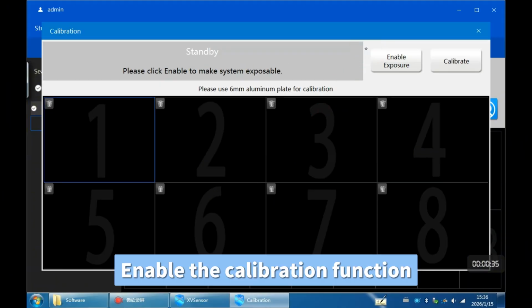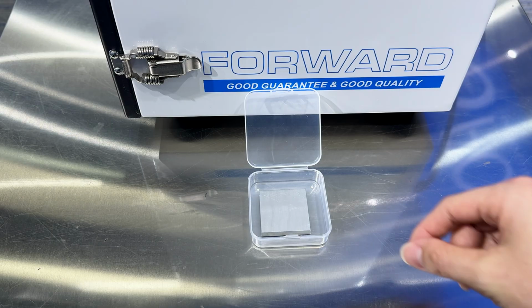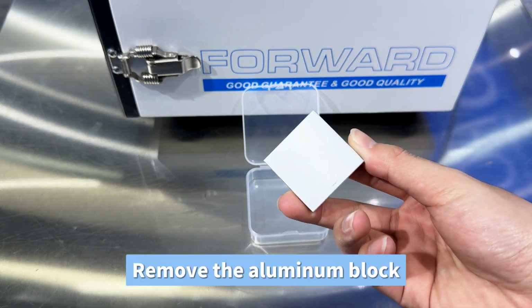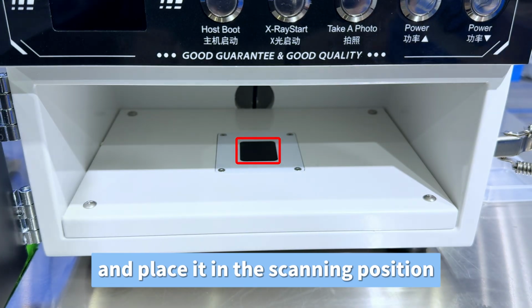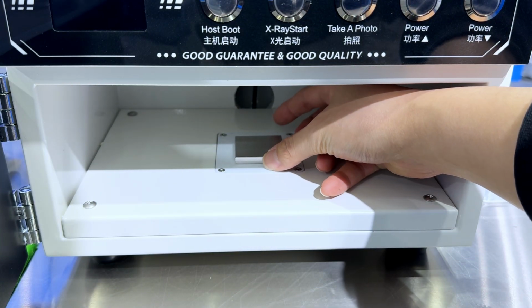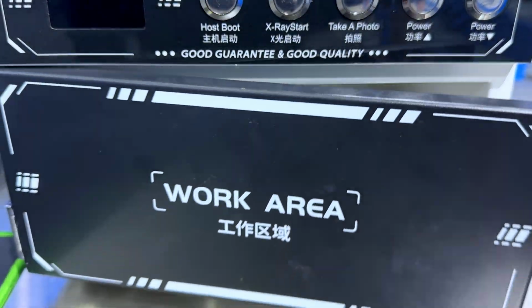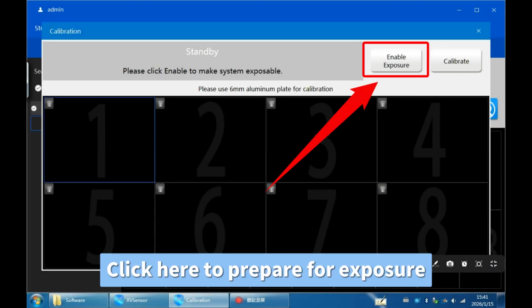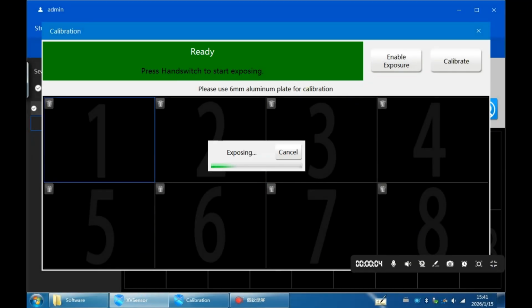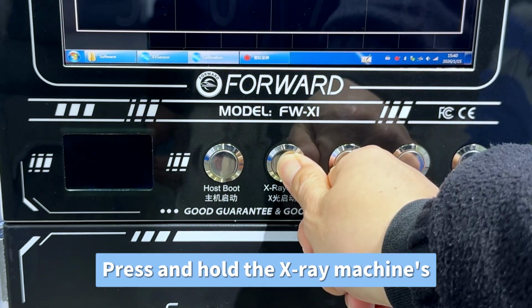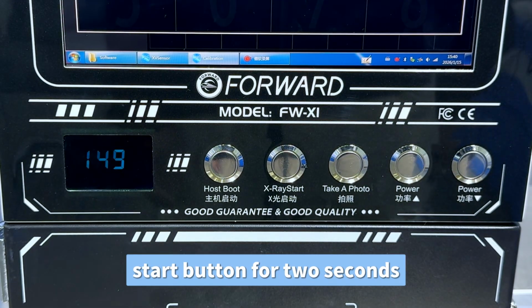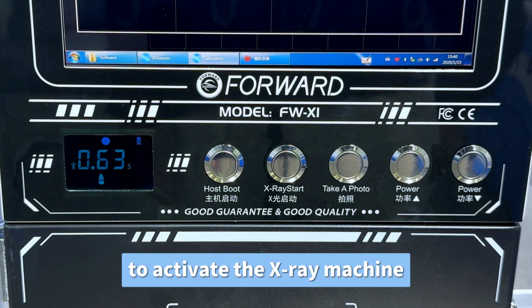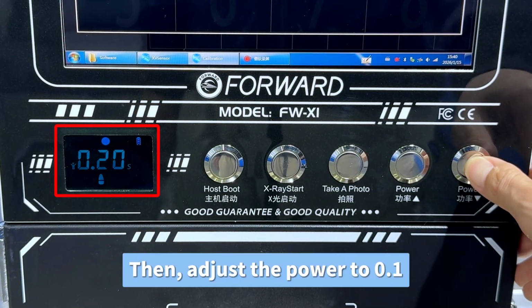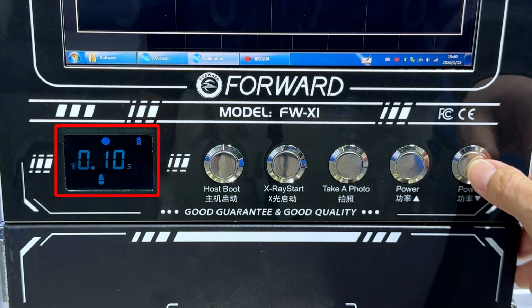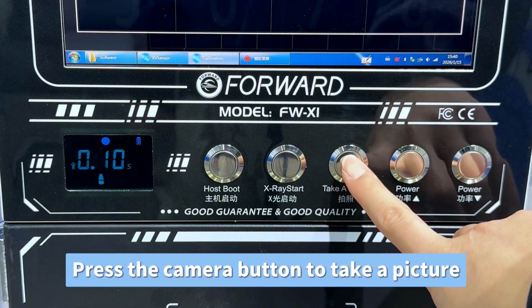Enable the calibration function. Remove the aluminum block and place it in the scanning position. Click here to prepare for exposure. Press and hold the X-ray machine's start button for 2 seconds to activate the X-ray machine. Then, adjust the power to 0.1. Press the camera button to take a picture.